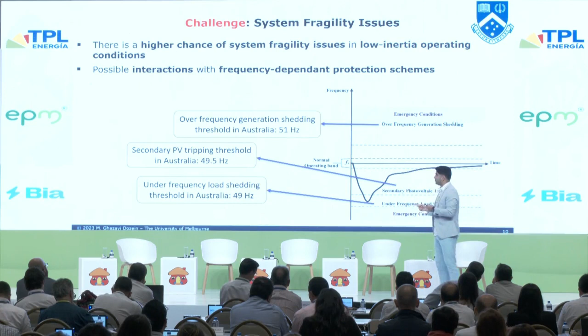This is what we have seen in Australian network operation, an event that happened in August 2018. This is a separation event. Power was being transferred from Queensland (QLD) to New South Wales (NSW). Because of some weather condition, QNI, the interconnector between Queensland and New South Wales, tripped. Queensland faced an over-frequency condition due to generation surplus, while the rest of the system faced an under-frequency condition. Then, four seconds after the Queensland separation, South Australia also separated because of the frequency drop and a very sharp active power rise through Heywood, the interconnector between South Australia and Victoria.